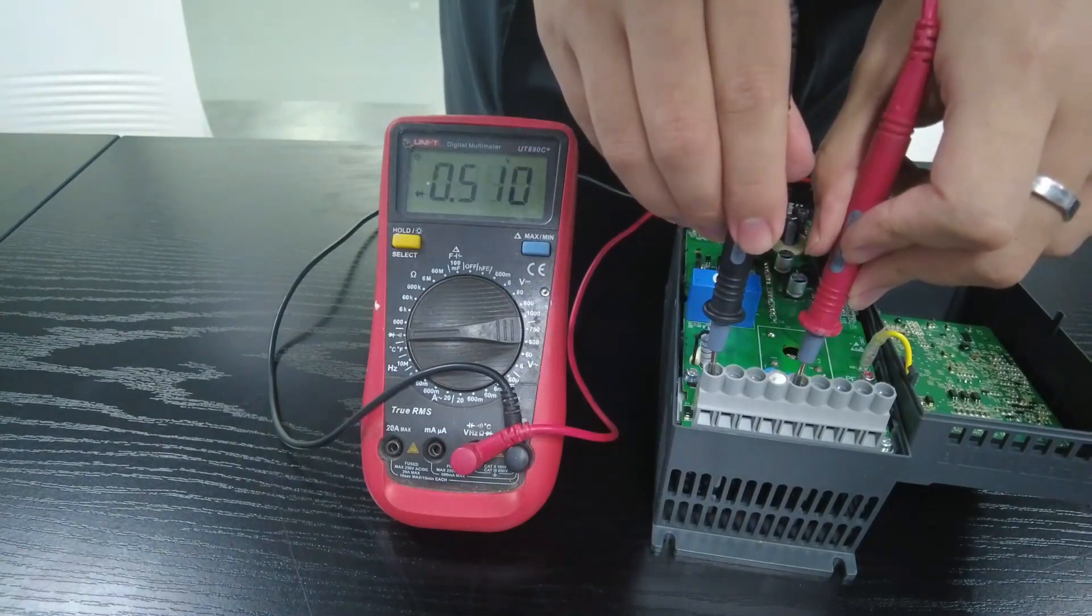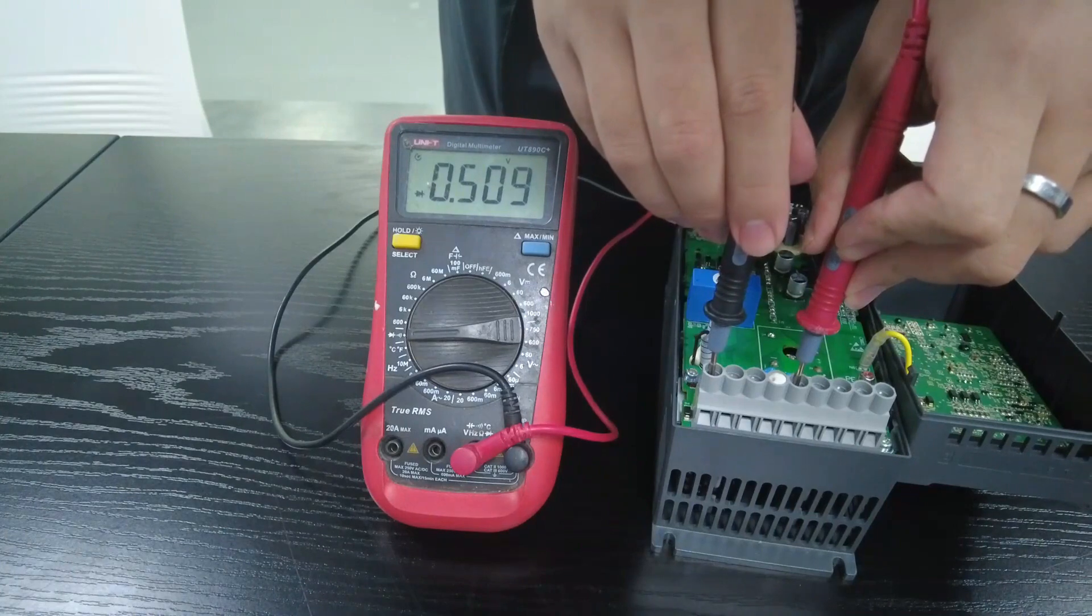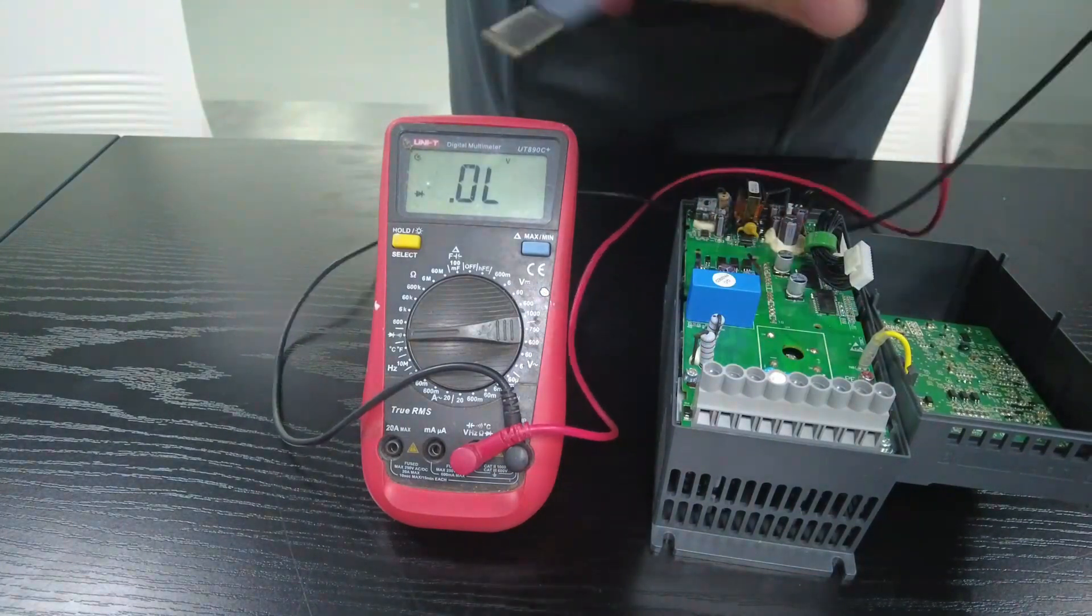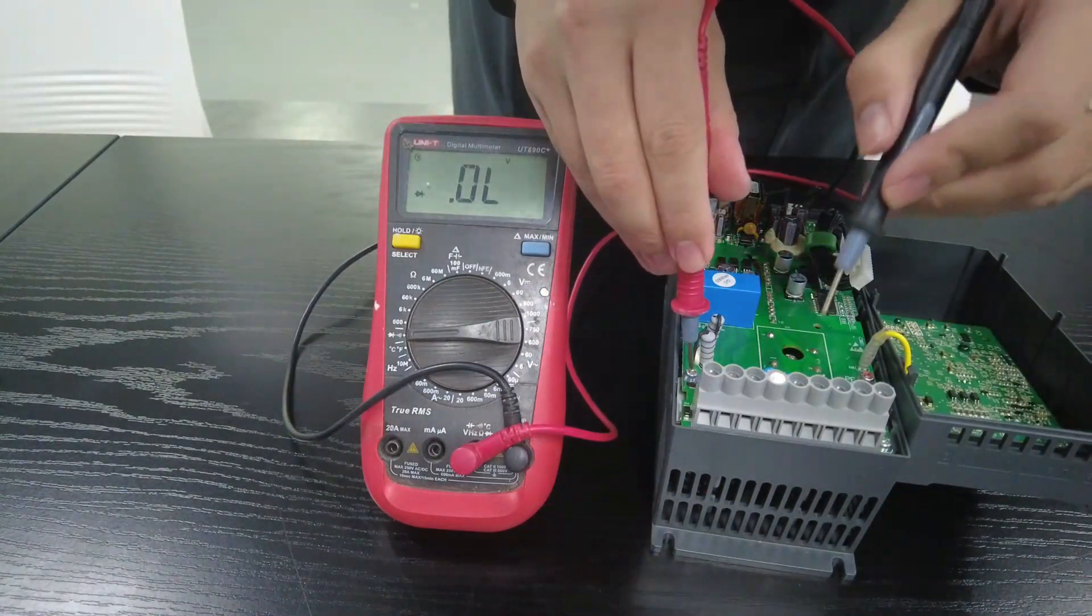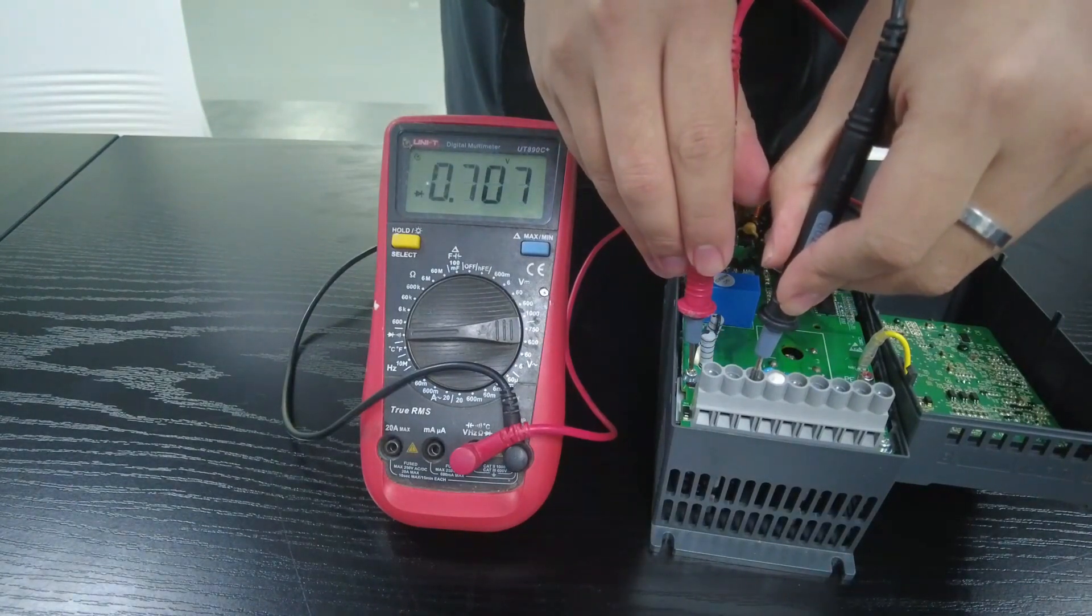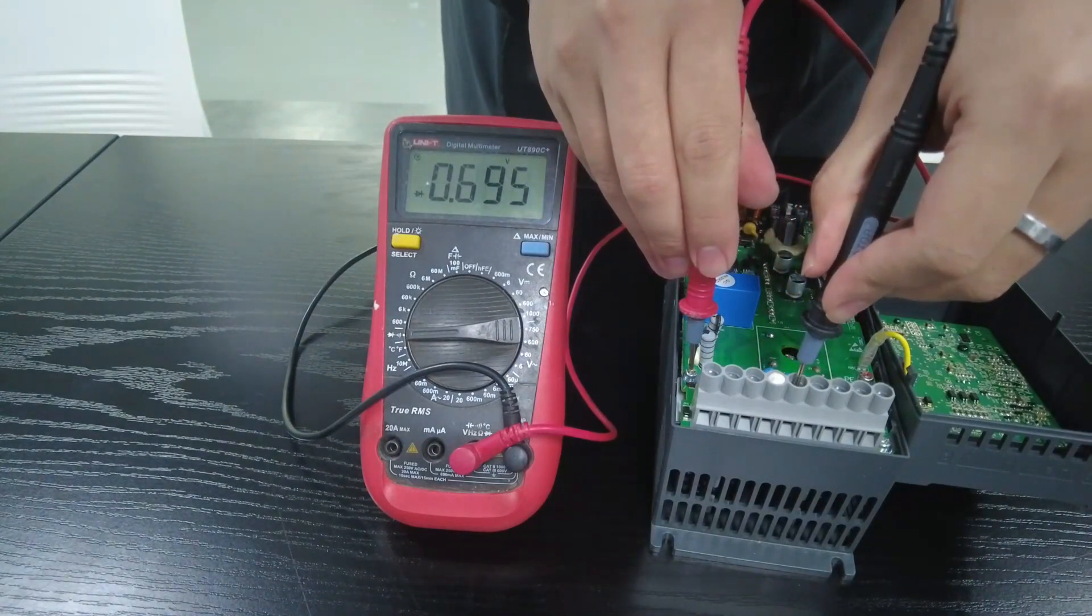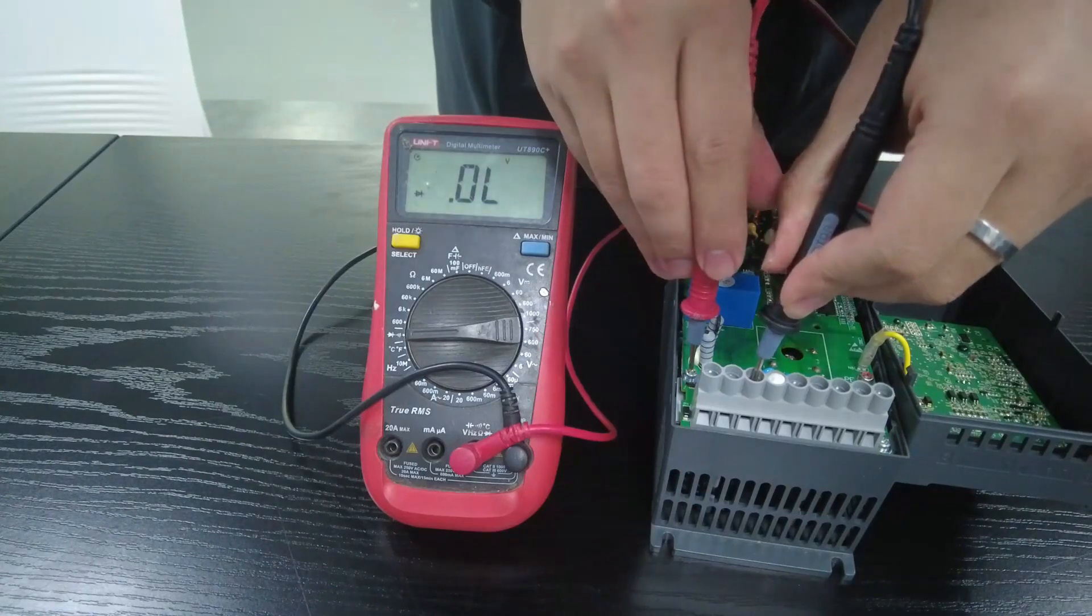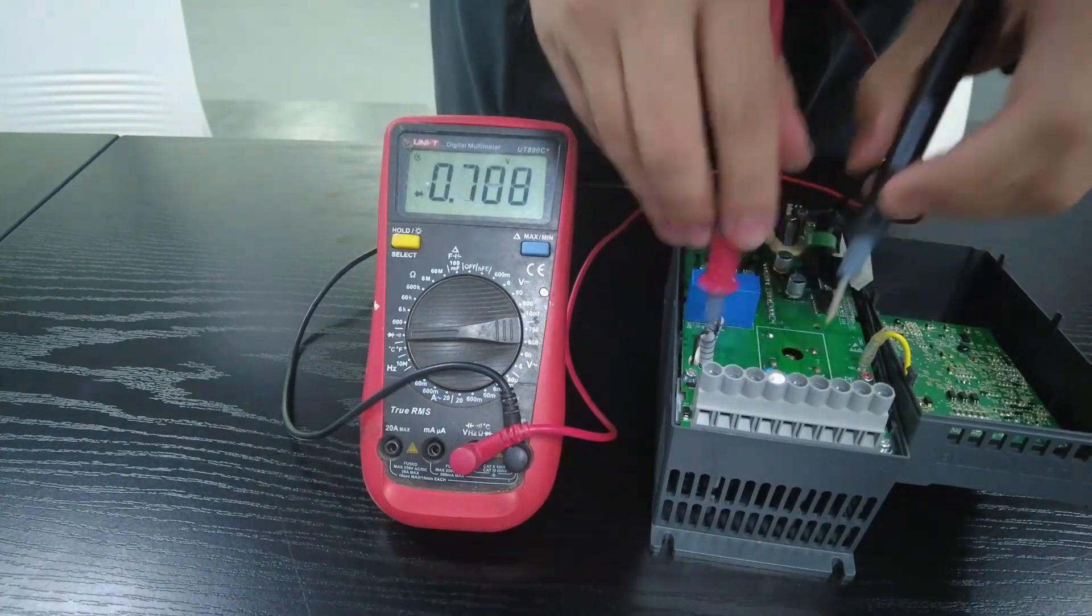Then connect the red test lead to the negative terminal and then use the black test lead to test the three terminals R, S, and T. This is normal if the measured values are all around 0.5. If the measurement values are all the same, it is normal.